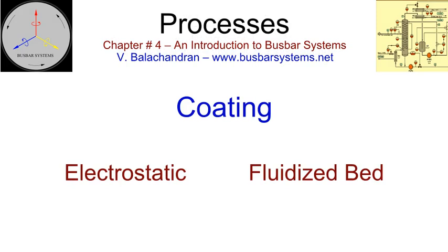Coating. The discussion is limited to the coating of bus bars for insulation. Coating, however, additionally improves the emissivity for better heat dissipation and provides protection against the corrosive environment. Medium voltage, air-insulated, metal-enclosed bus are designed to meet the specified BIL requirements.